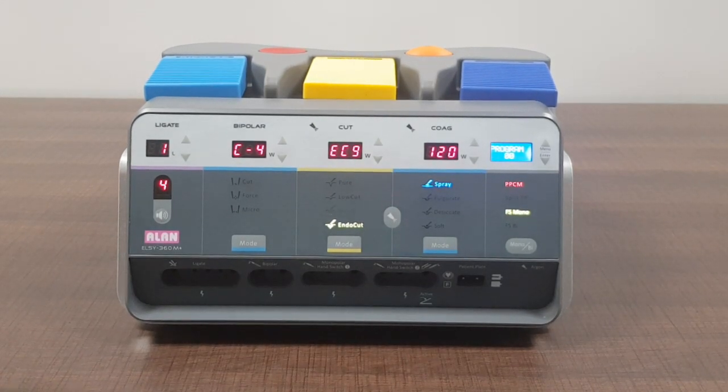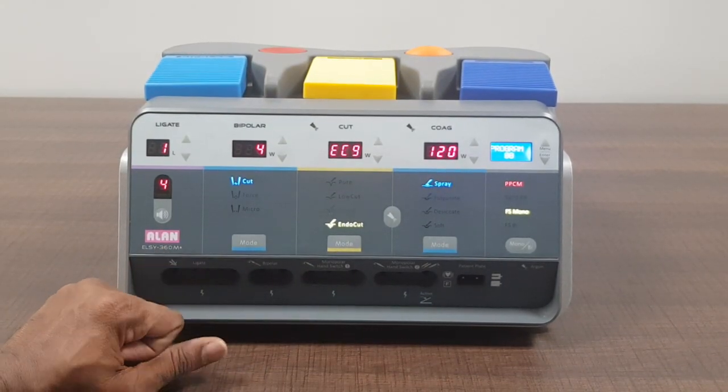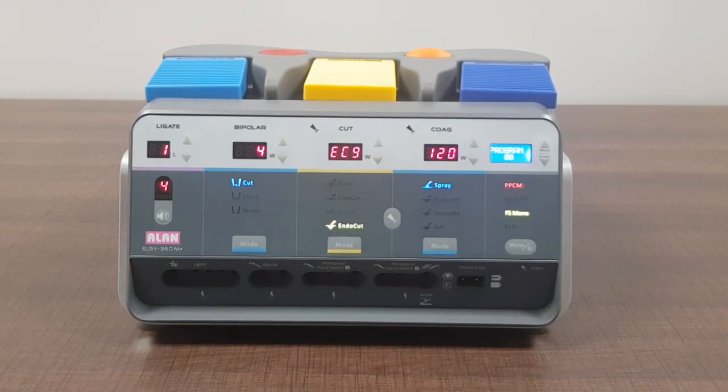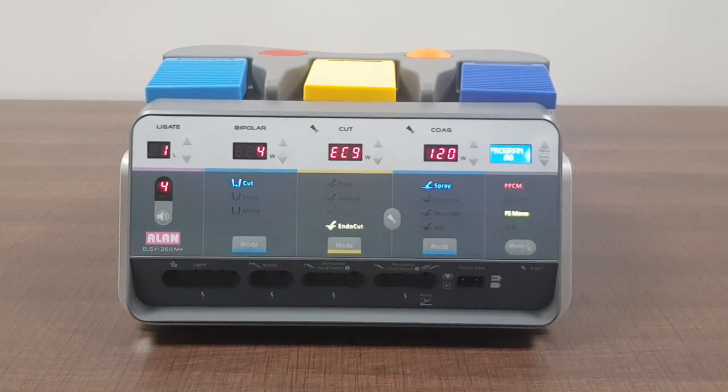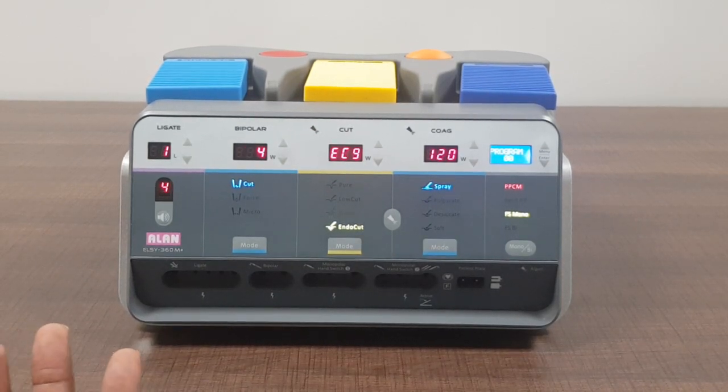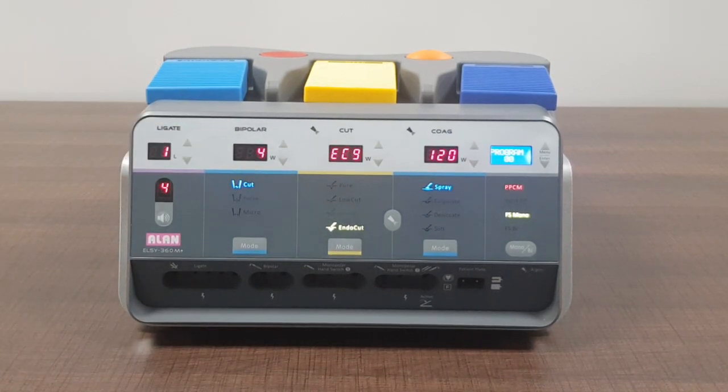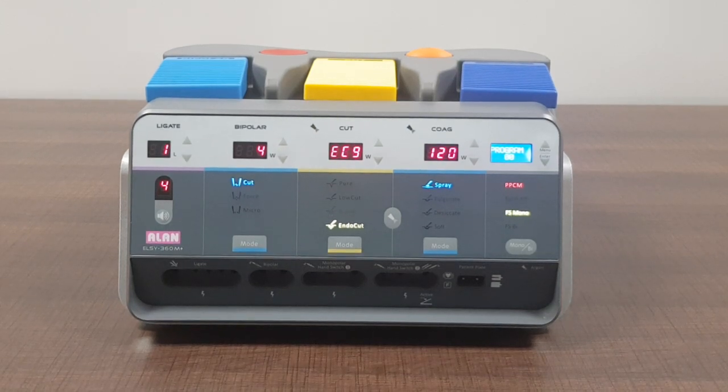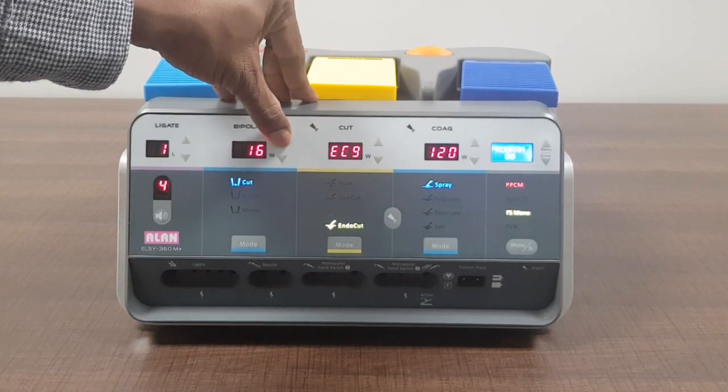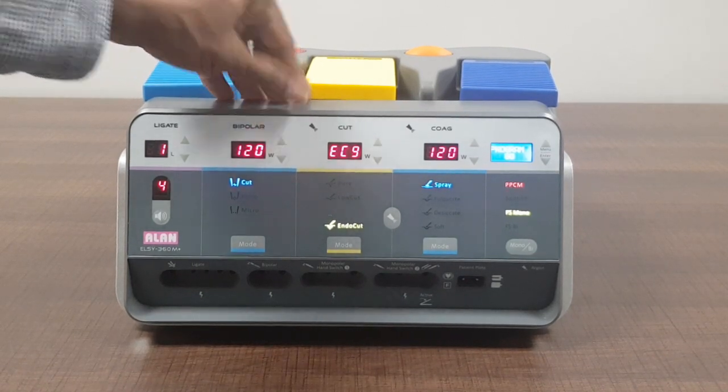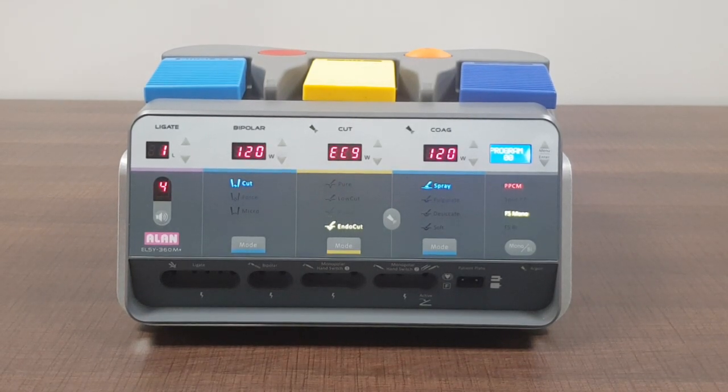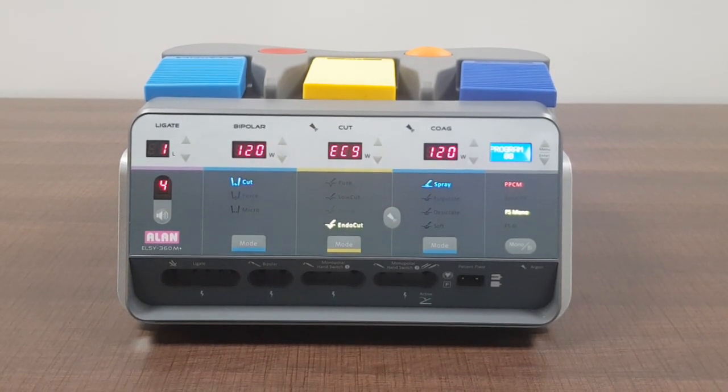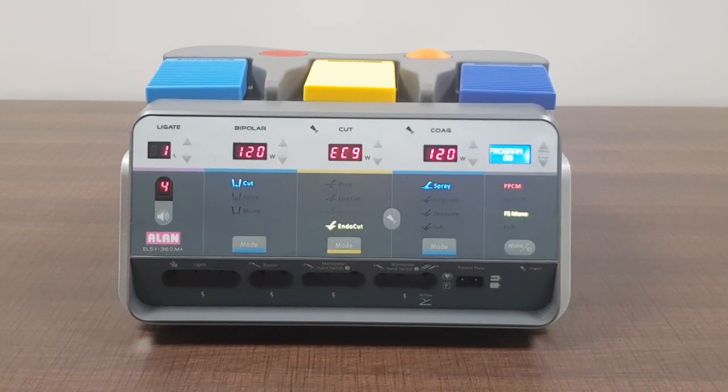Next coming is a bipolar. This is most commonly or widely accepted technology right now when compared to monopolar because monopolar is a little riskier because of the high voltage and the current has to pass through the patient's body and then collected in the patient plate and taken back to the machine. Wherein in bipolar it is much safer because of the less voltage and the kind of technology that we use in bipolar. We have very commonly used as cut. I will show you the maximum voltage, it's 120 watts. Mostly bipolar is used for coagulation but there is a standard cut feature given. So let's say for example if you want to cut using bipolar then there is a specific scissor that comes, you can use that and cut the tissue using bipolar.